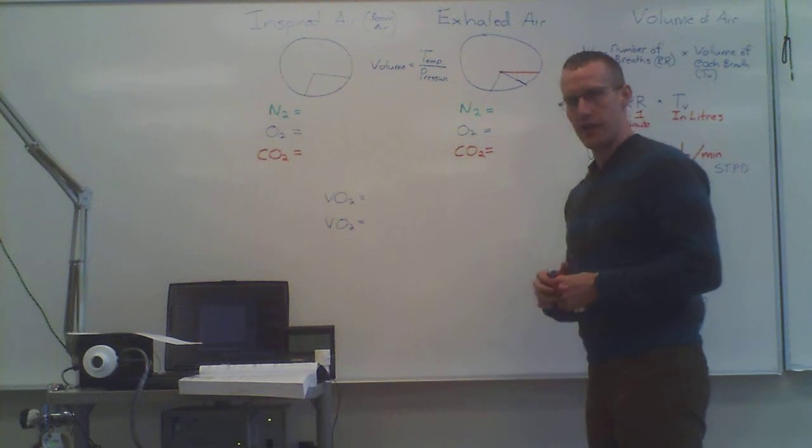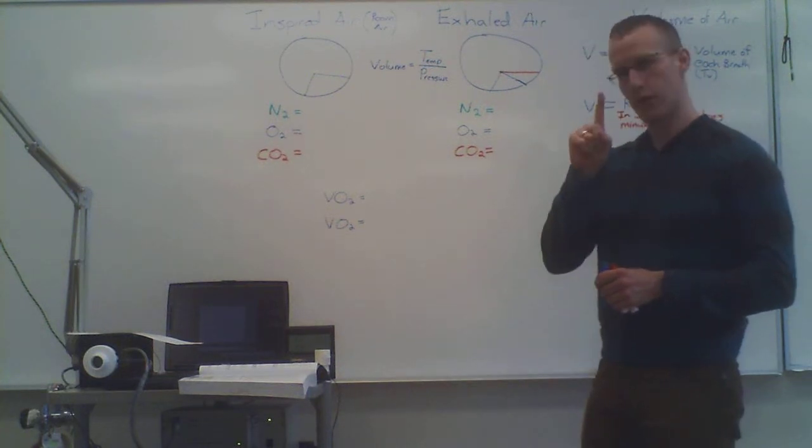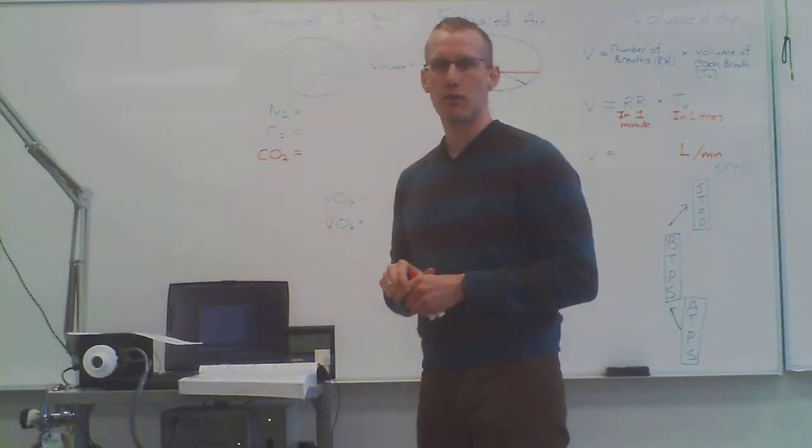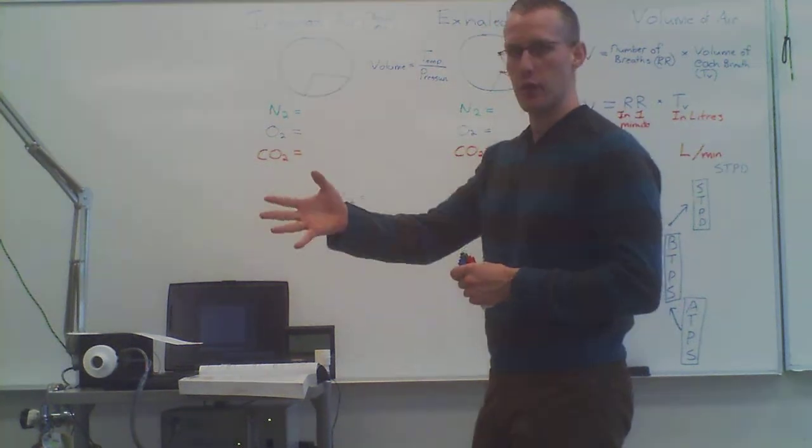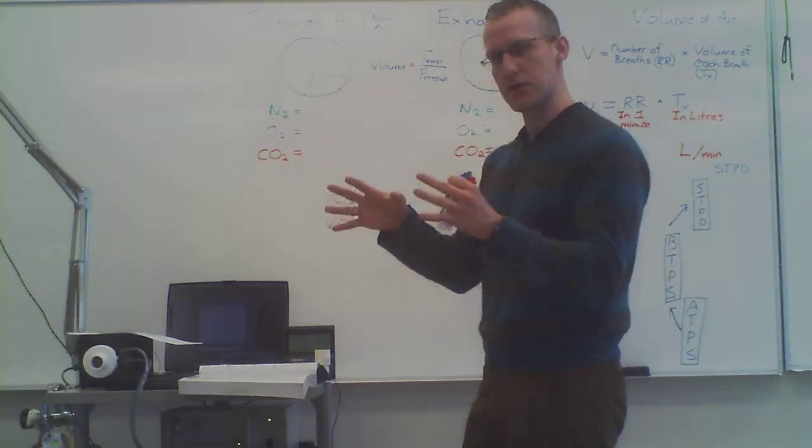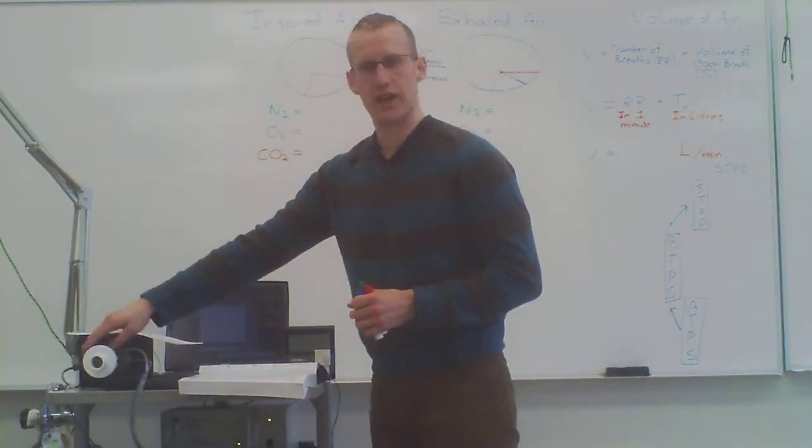So what does the cart measure? It measures three things. The first one is it measures the volume of air that somebody is breathing out. So the mouthpiece traps all the air and it goes through this device called the pneumotach.